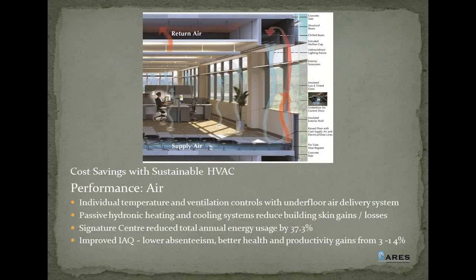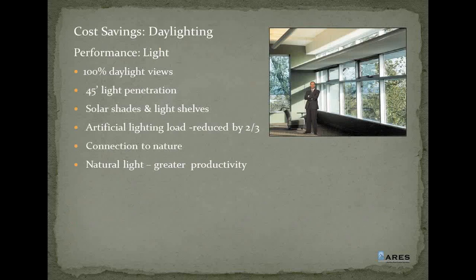The thermal comfort that comes out of the system is every single cube has its own diffuser in the floor. If somebody's hot, they can open it and get more air. If somebody's cold, they can close it off, turn off their air. If you need more air, simply pull up a floor tile, put a new floor tile in with a diffuser, you've got more air. Totally controllable, very easy for people to be satisfied for whatever their temperature need may be.